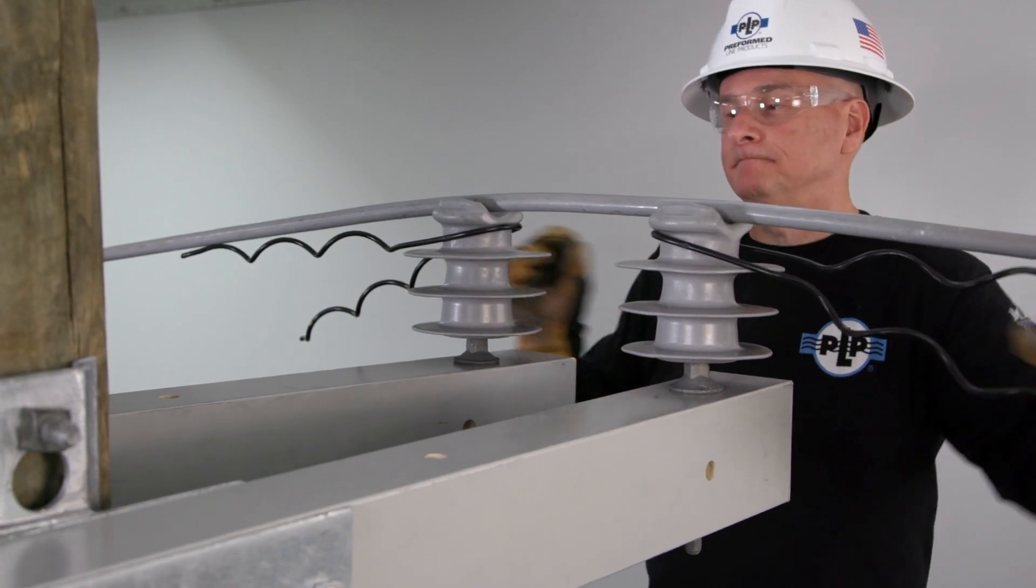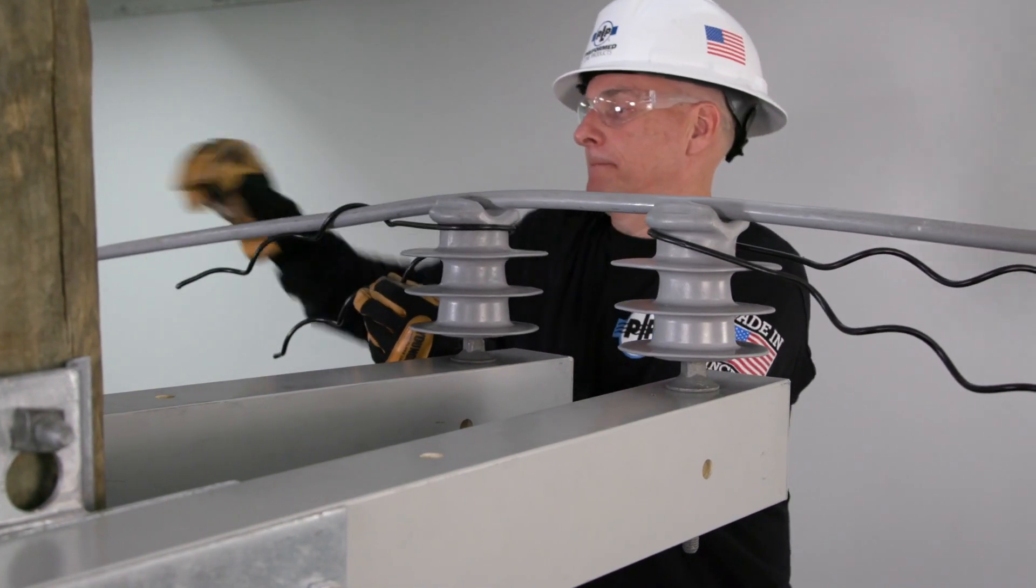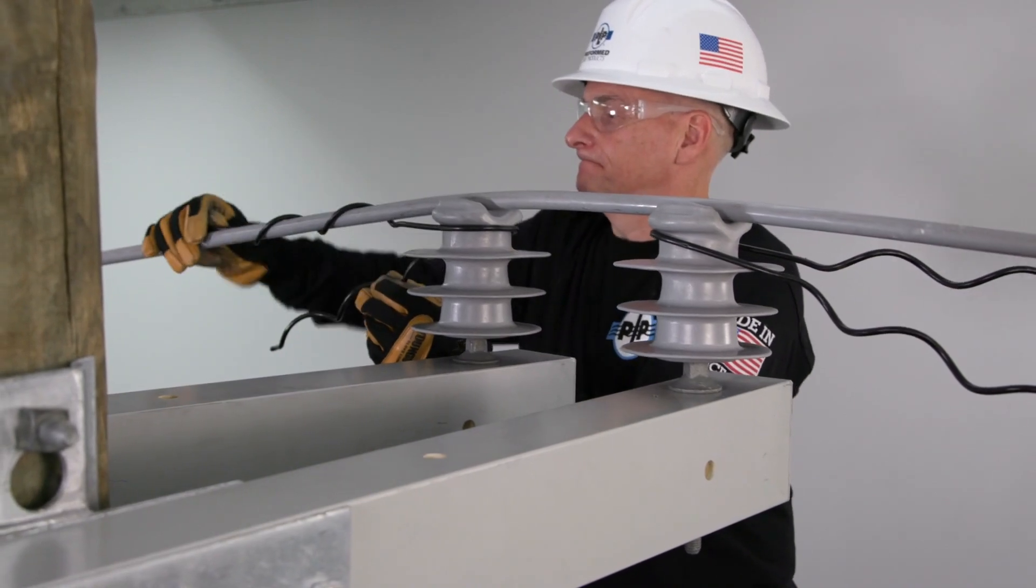Begin wrapping the first leg of the tie onto the conductor in a counterclockwise rotation starting at the crossover point. Be sure to snap the end of the leg into position with slight thumb pressure.